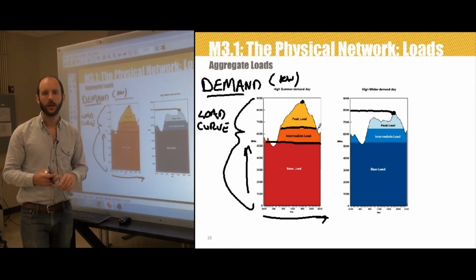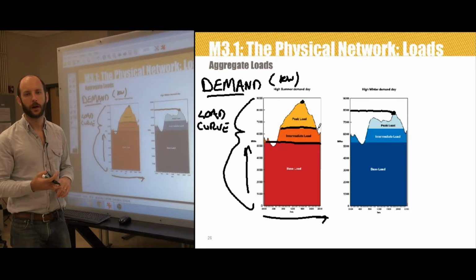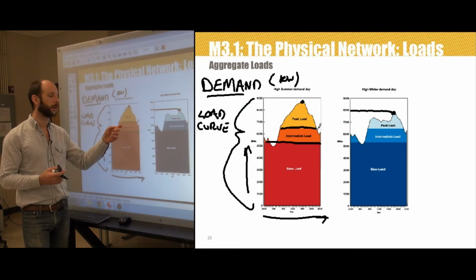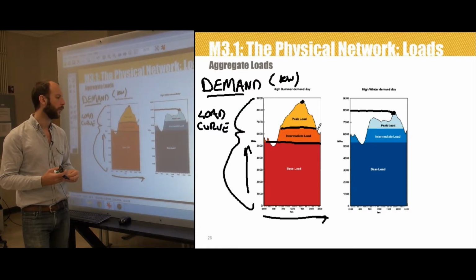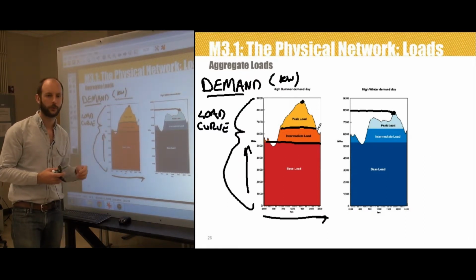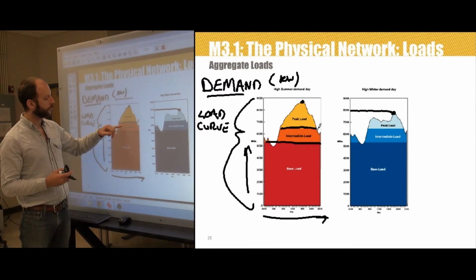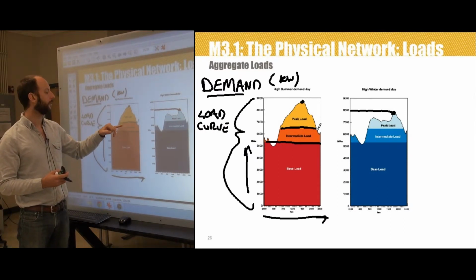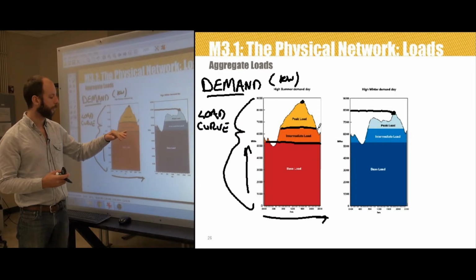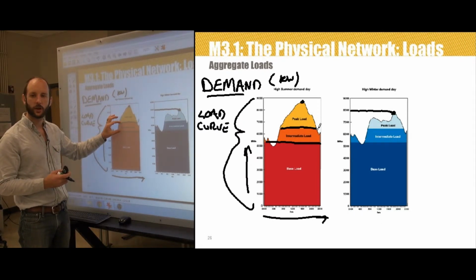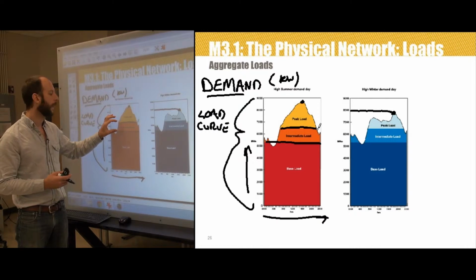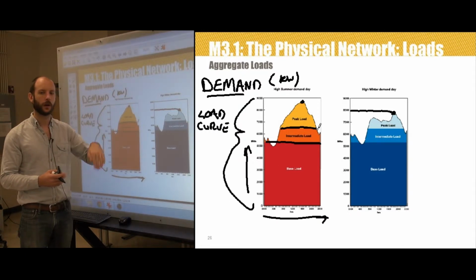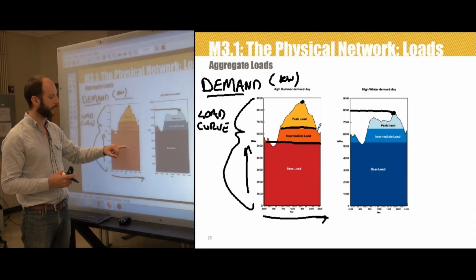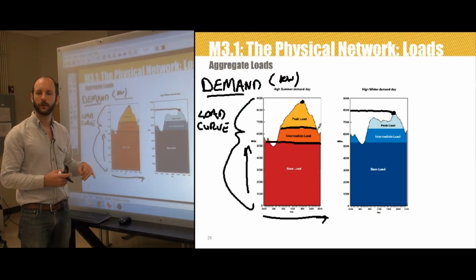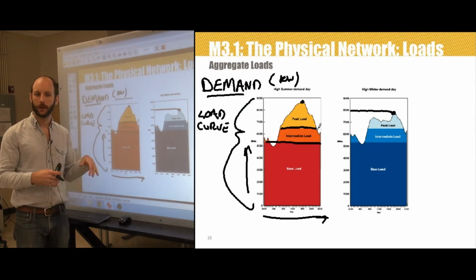Intermediate load here is often met with the use of smaller, fast-acting plants. These might be combustion turbines, for example, or smaller natural gas turbines. The electricity produced by these isn't going to benefit from the economies of scale that base load does. So this electricity actually costs a little bit more to produce, and I'm willing to pay a little bit more because I can ramp these generators up and down faster than I can the base load generator. So they're a little bit more responsive, so I pay for that.